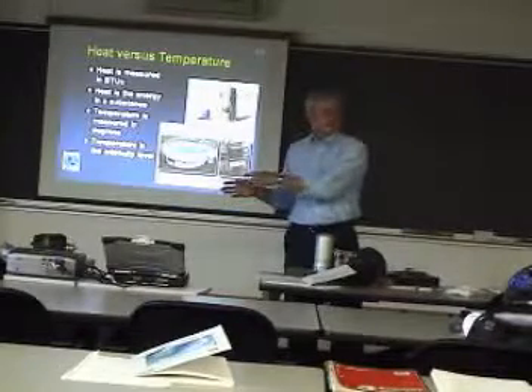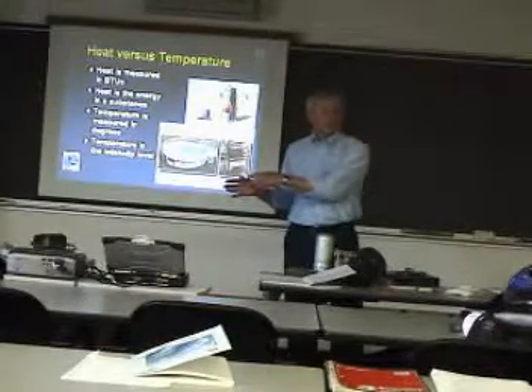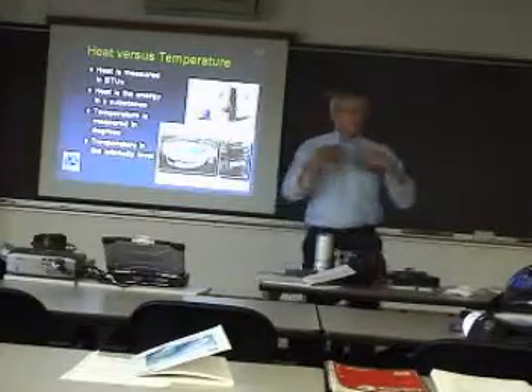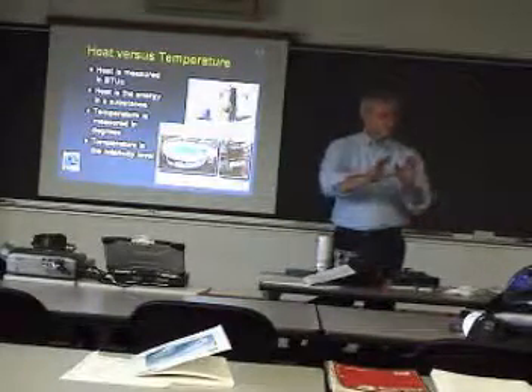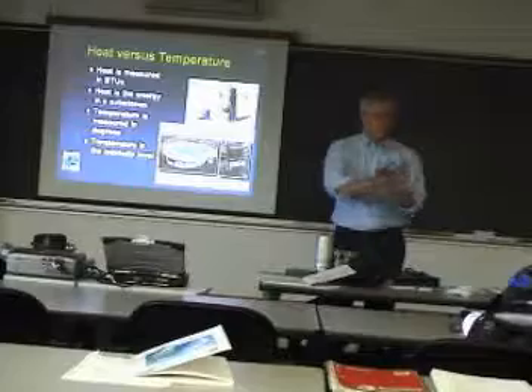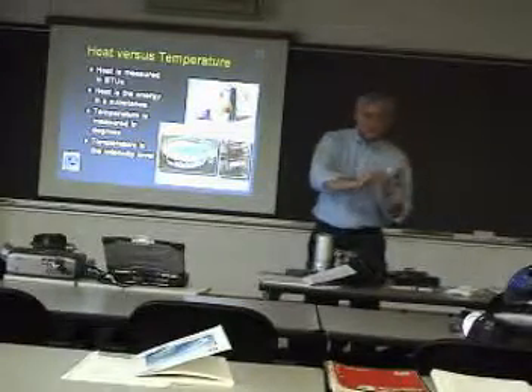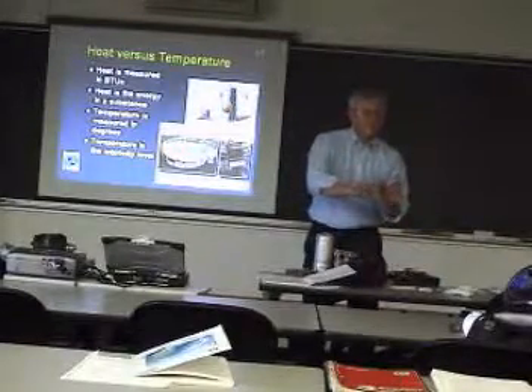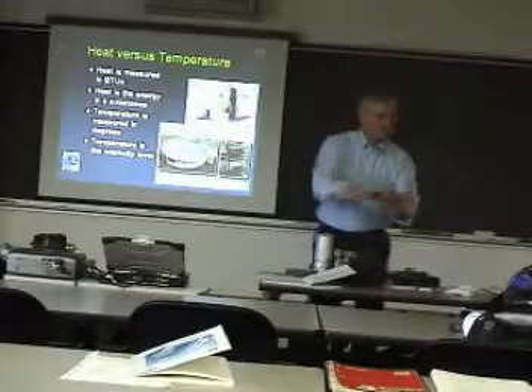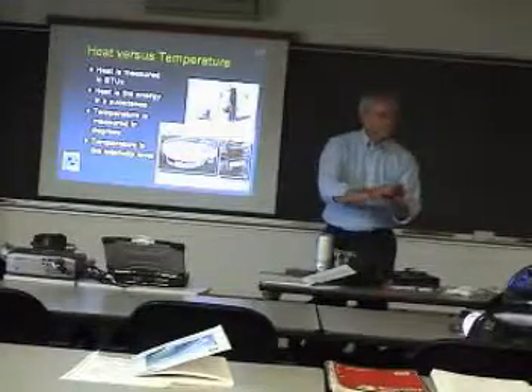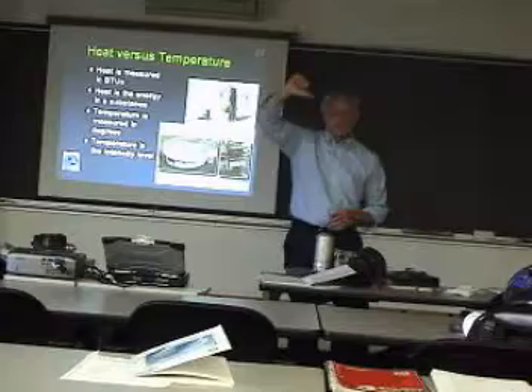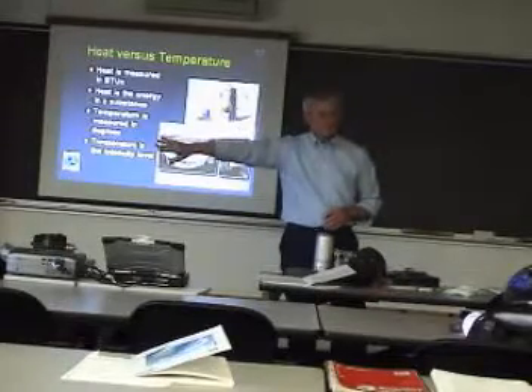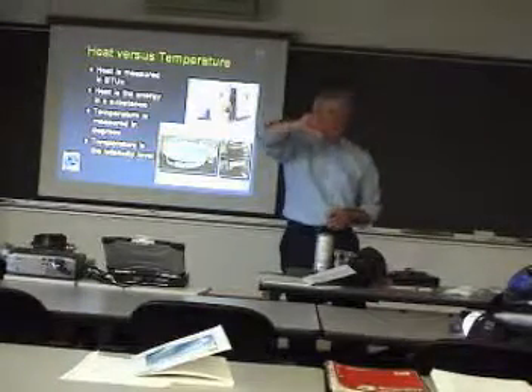So is it absorbing any heat energy? No. So now we've got refrigerant that's been pumped into the condenser, and it's staying there. So we are not pumping any new heat energy into it. So the pressure on the high side will be, even though you've got it plugged off on the orifice, going to be lower than normal.